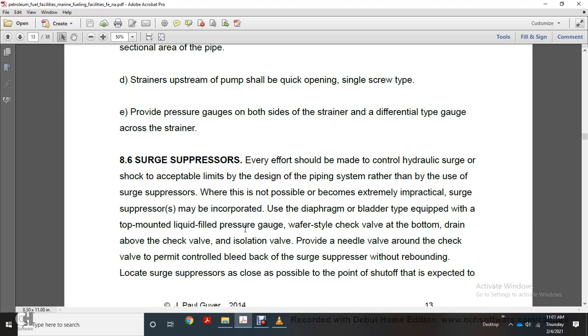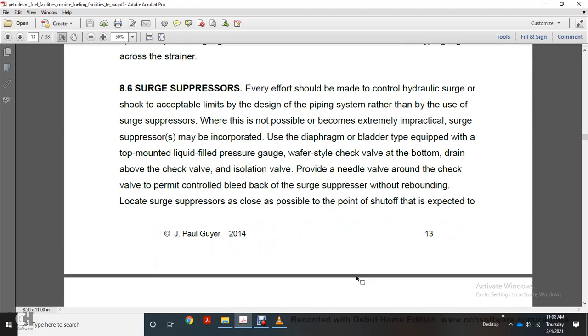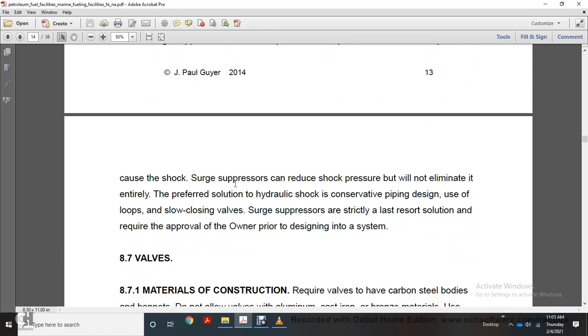Alright, surge suppressors. Every effort should be made to control the hydraulic surge within the limits of the design of the piping system rather than use surge suppressors. When this is not possible, surge suppressors may be incorporated, of the diaphragm bladder type, equipped with a top-mounted liquid-filled pressure gauge, with a check valve at the bottom of the drain. Above the check valve, add an isolating valve and a needle valve around the check valve to permit and control bleed-back from the surge suppressor without rebounding. Locate the surge suppressor as close as possible to the point where shutoff is expected to cause shock. Surge suppressors can reduce shock pressure but will not eliminate it entirely; provide a solution with conservative hydraulic piping design.